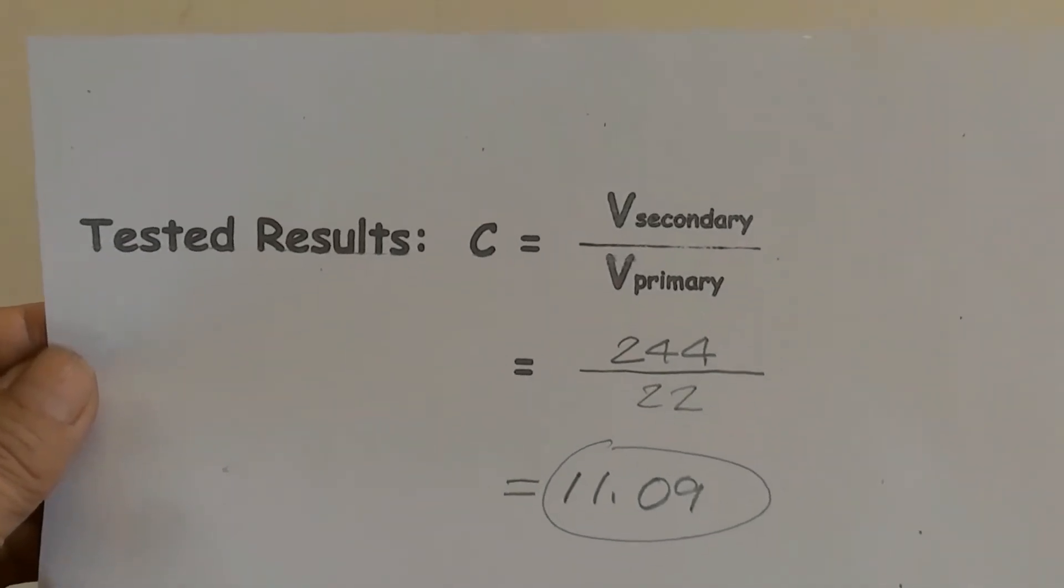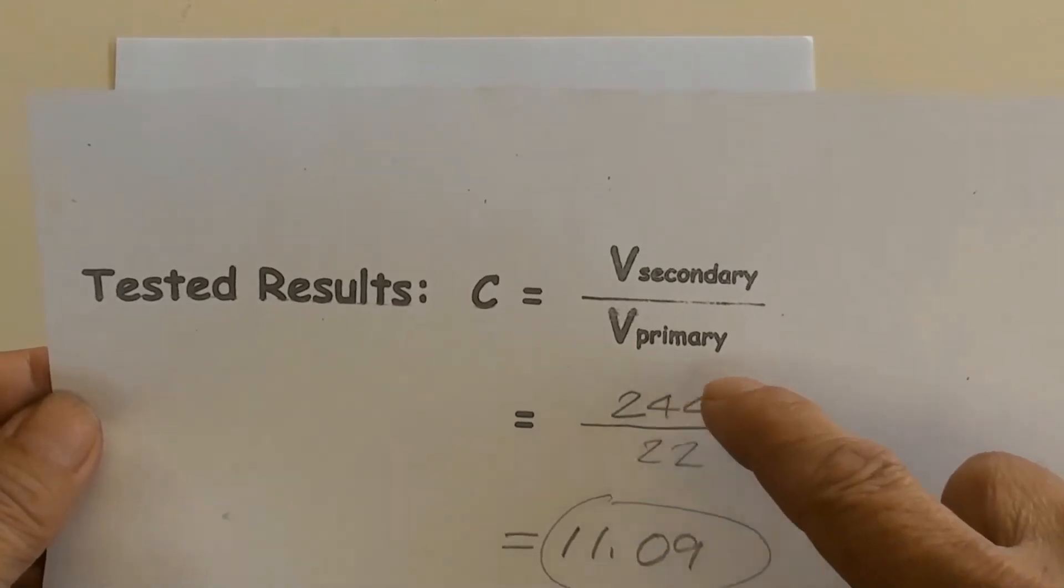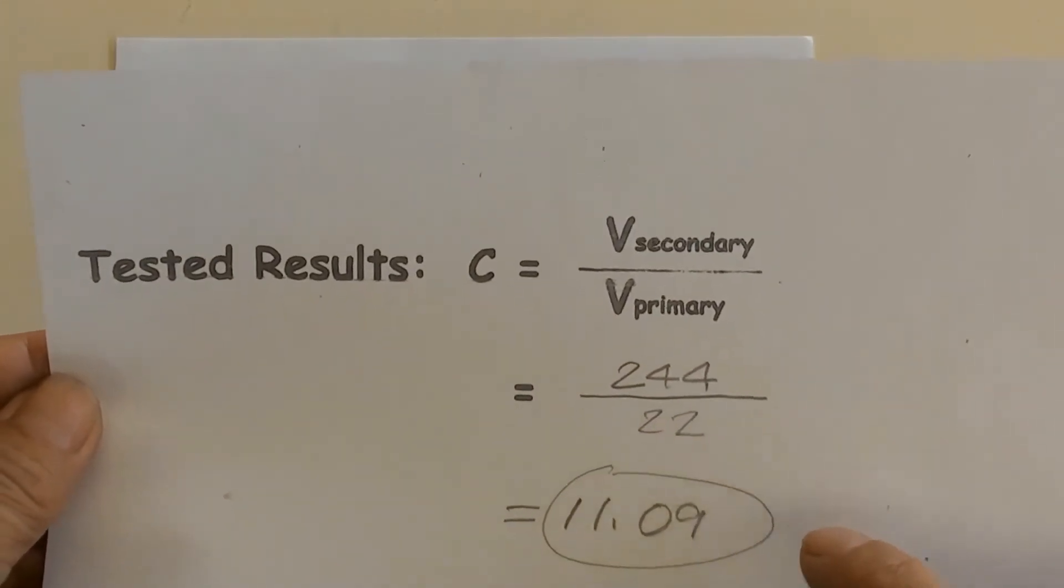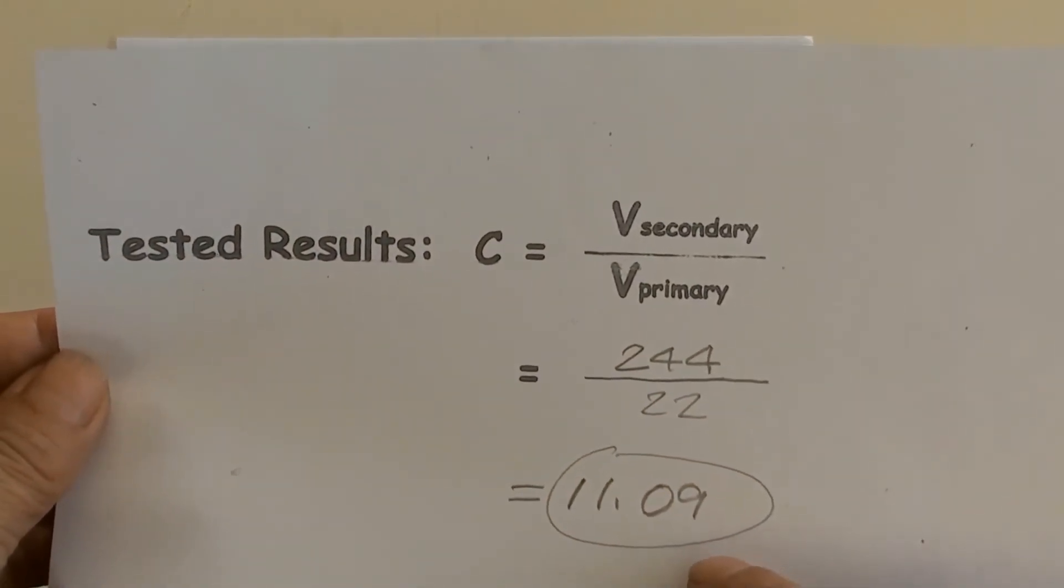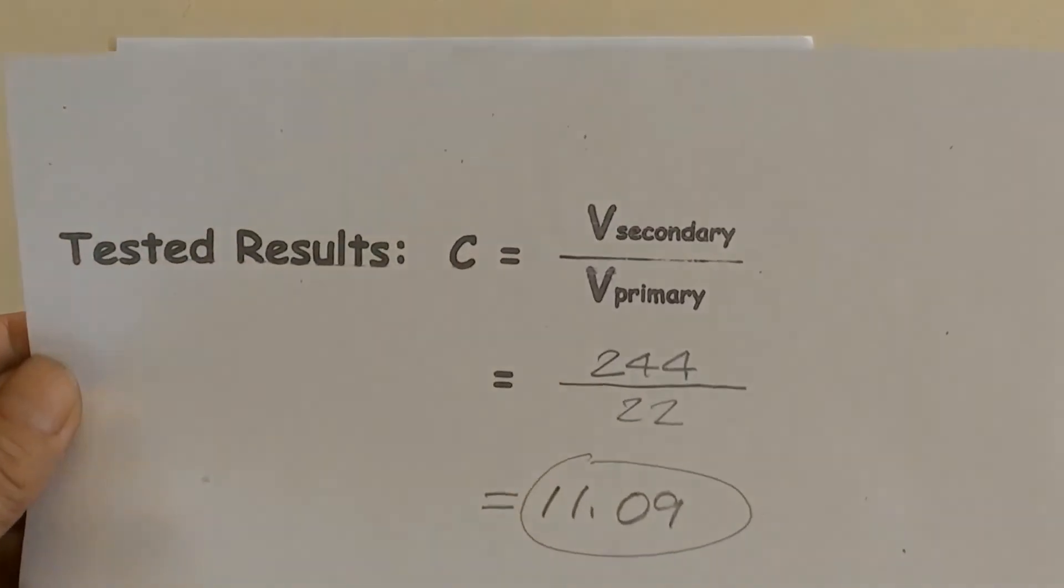Tested results are filled in this formula. V secondary over V primary equals 244 volts over 22 volts equals 11.09, so C is 11.09.